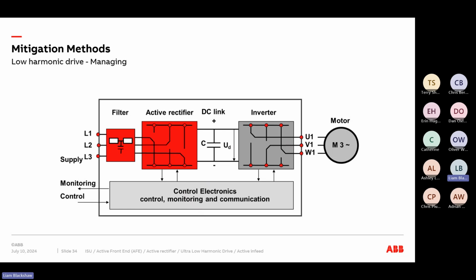Now, it has been said out there, and it has been known, that some drives without the appropriate filtering can cause nuisance harmonics at higher orders, maybe above the 50th to the 100th order. But there are manufacturers out there, and this is ABB included, that will have a filter in their setup that eliminates the need to worry about those harmonics at higher orders. So it's a very simple solution, just 3 cables in, 3 cables out, and harmonics are less of an afterthought, at least anyway, and you're not having to address things reactively but more proactively. But a typical waveform for that alone could be somewhere in the region of 3 to 5% total harmonic distortion.